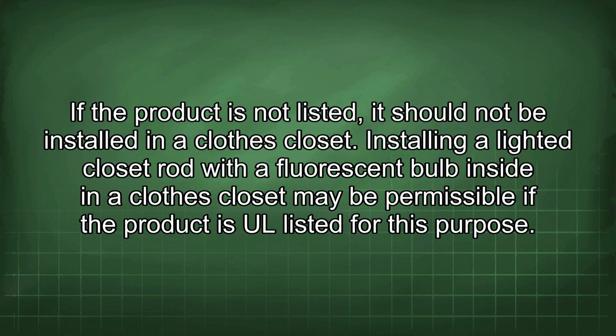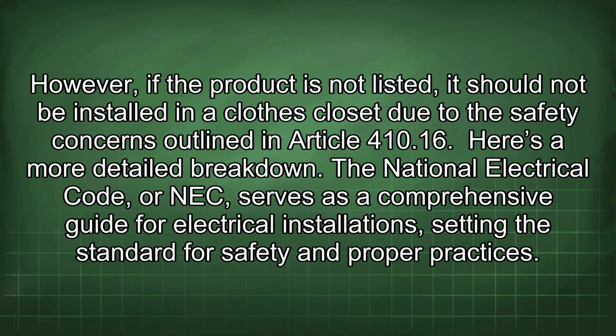Installing a lighted closet rod with a fluorescent bulb inside in a clothes closet may be permissible if the product is UL listed for this purpose. However, if the product is not listed, it should not be installed in a clothes closet due to the safety concerns outlined in Article 410.16. Here is a more detailed breakdown.